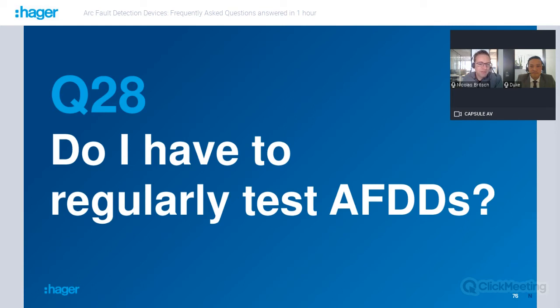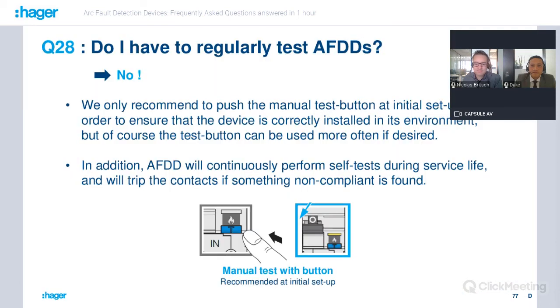Duke, do I have to regularly test AFDDs? Actually, the answer is no. But pay attention. We only recommend pushing the manual test button, as you see here for RCD, once at initial setup. After that, during its service life, the AFDD will continuously perform self-test by itself automatically and will trip the contacts if something non-compliant is found. So it's totally automatic.